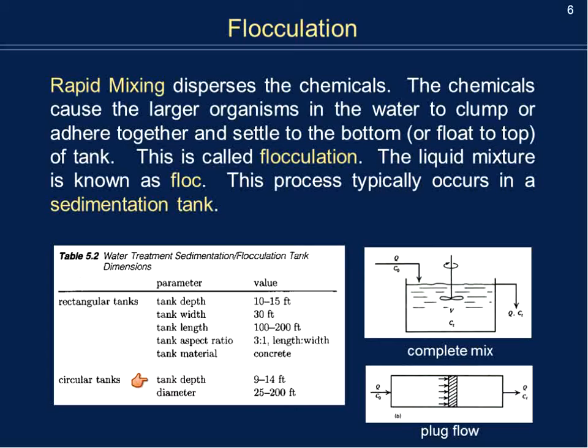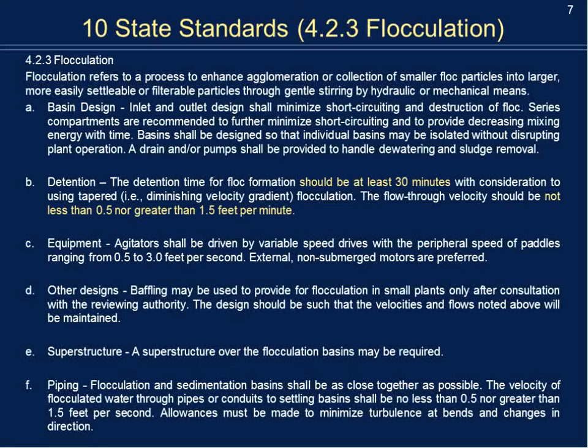For a circular tank, the depth is typically between 9 and 14 feet, and the diameter can range from 25 to 200 feet — a substantial difference depending on how many tanks you're running and how much property you have. The Ten State Standards we need to adhere to in New York particularly concern detention time and flow-through velocity. Detention time should be at least 30 minutes, and flow-through velocity should be no less than 0.5 and no greater than 1.5 feet per minute.